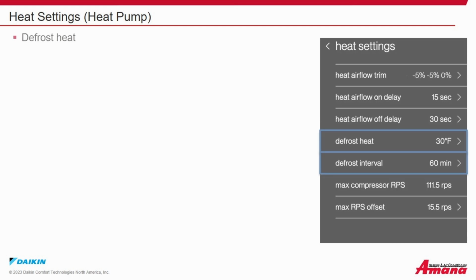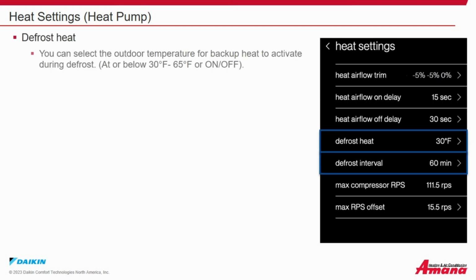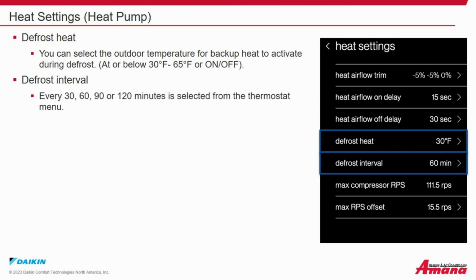Heat settings for heat pumps. Defrost heat. You can select the outdoor temperature for backup heat to activate during defrost, at or below 30 degrees Fahrenheit to 65 degrees Fahrenheit, or on or off. Defrost interval. Every 30, 60, 90, or 120 minutes is selected from the thermostat menu.